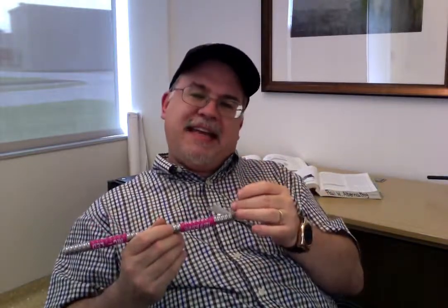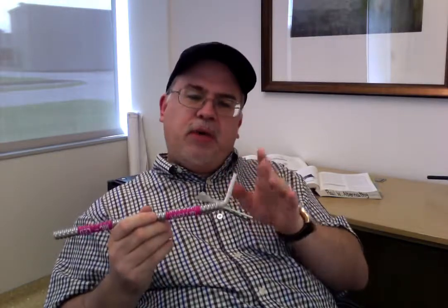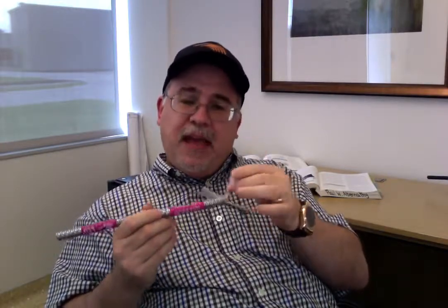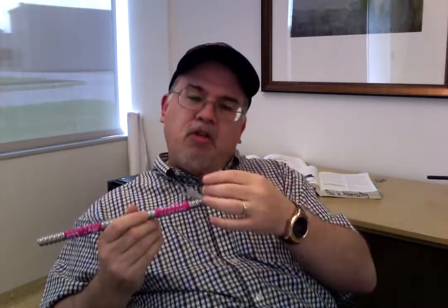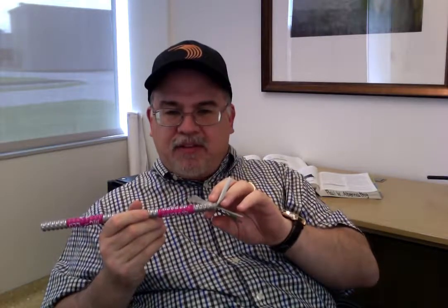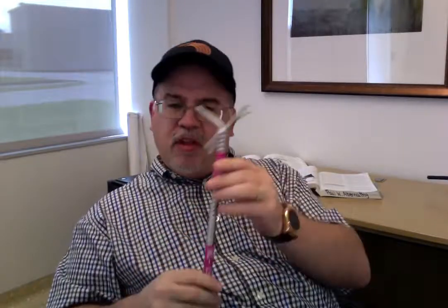And so what it's basically telling you is that as long as you put the Class 2 or Class 3 cables with a minimum of 30 mil sheathing, it's not insulation, it's a sheathing. As long as you put that jacket sheathing on these conductors, and you can put it in the same cable assembly, that's enough separation necessary, and you don't need to have a 2-inch separation. So they allow these conductors, the low voltage and the standard voltage, together in the same cable and not have a problem. So this is allowed under National Electrical Code applications.